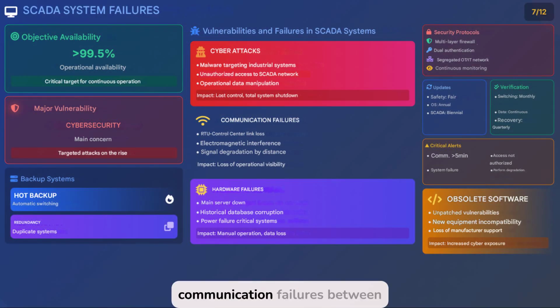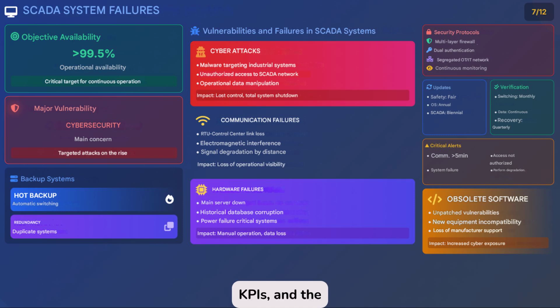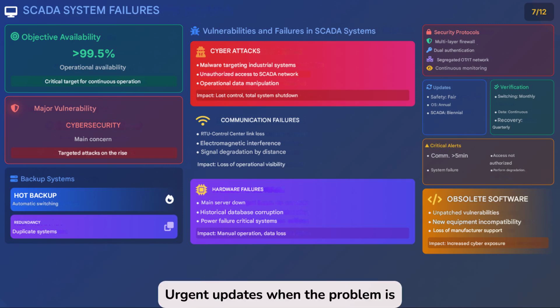Added to this are communication failures between RTUs and the control center, interference, or signal degradation. The loss of visibility forces operations to operate in reactive mode, increasing costs and reducing efficiency. Likewise, hardware failures, such as server downtime or loss of databases, lead to manual modes that affect traceability, KPIs, and the ability to perform technical and financial analysis. Another risk factor is outdated software, which leaves many plants without support, without security patches, and with compatibility issues. Urgent updates when the problem is already active are much more costly than preventive planning.